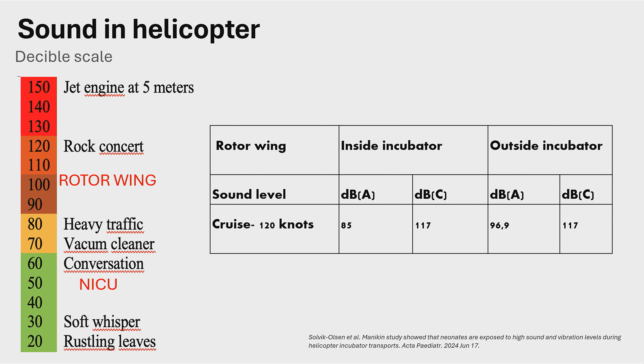So when we are measuring the sound within the helicopter, we found that during the cruising speed, the sound level within the incubator is around 85 decibels, and about 10 decibels more outside the incubator. But we do have peaks that are up to 117 decibels. And I put that also on the graph. And that is almost as much as there is on a rock concert. And then I'm going to say something about the clinical evaluation of the baby.